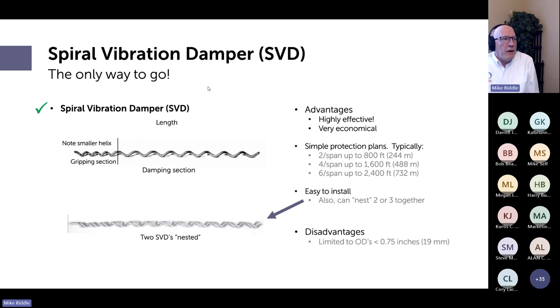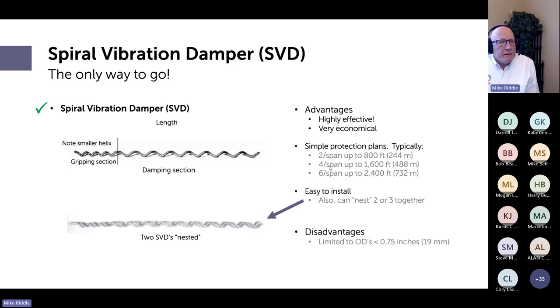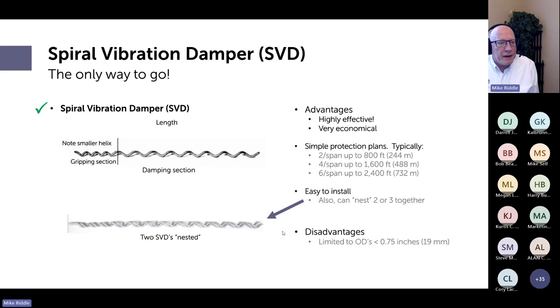SVDs are the only practical vibration damper option for ADSS. They have a large helix and a smaller helix gripping section, and they can be nested. The placement plan is straightforward: two per span up to 800 feet, four per span up to 1,600 feet, six per span up to 2,400 feet. They're relatively inexpensive and easy to install. The one limitation is that for 288-fiber cable the diameter may exceed three-quarters of an inch, which is normally the upper limit for SVDs — consult both the cable and accessory suppliers.